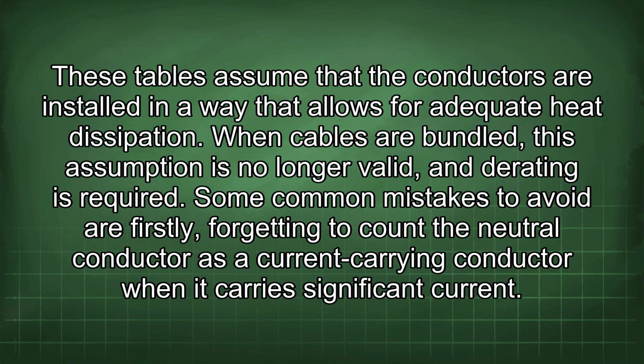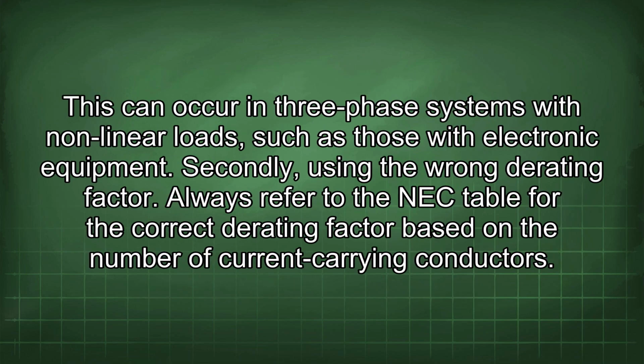Some common mistakes to avoid are, firstly, forgetting to count the neutral conductor as a current-carrying conductor when it carries significant current. This can occur in 3-phase systems with nonlinear loads, such as those with electronic equipment. Secondly, using the wrong derating factor. Always refer to the NEC table for the correct derating factor based on the number of current-carrying conductors.